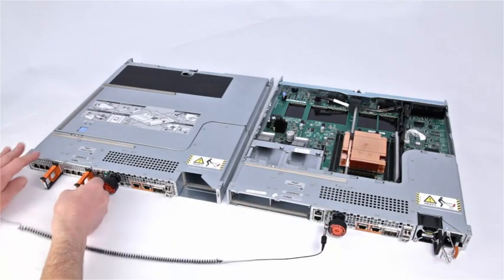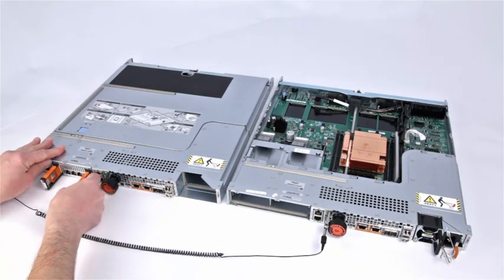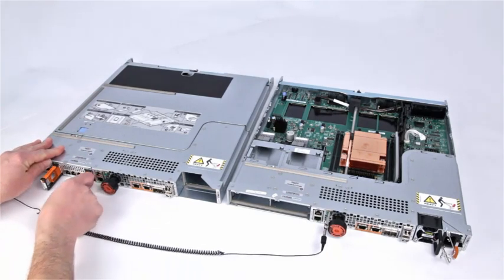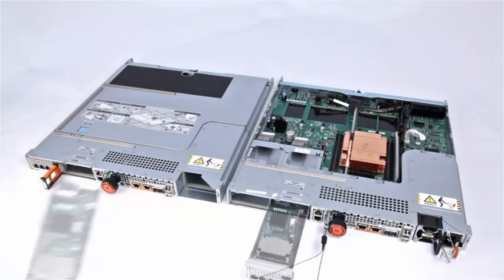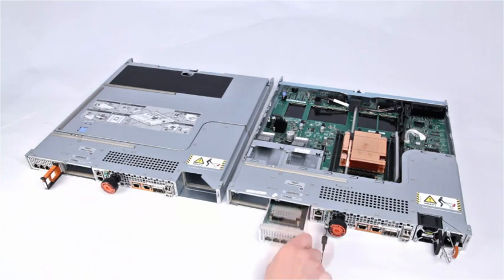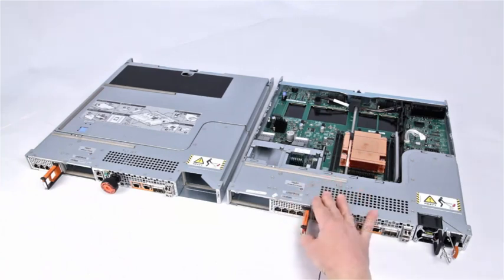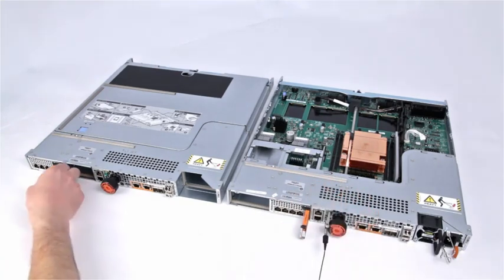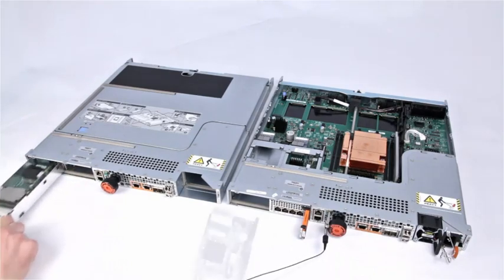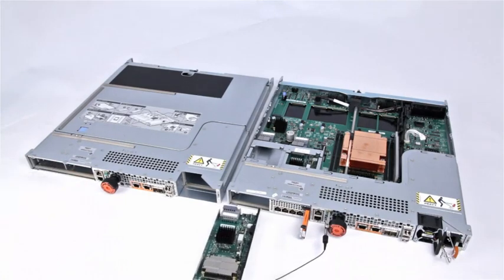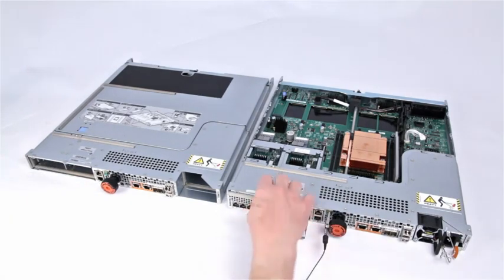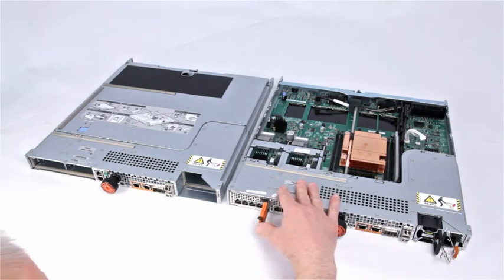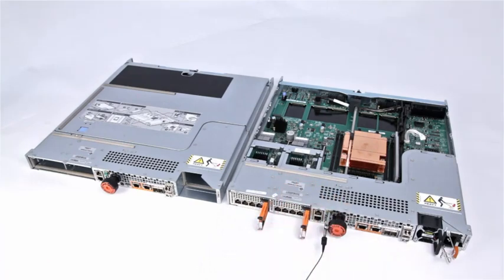Next, transfer each installed I.O. module to the exact same slot in the new SP assembly. Pull the trigger mechanism on the I.O. module handles to release them. Align the module with the empty slot of the replacement SP and carefully push the module into the slot. When the I.O. module appears seated, push and release the small button on the handle. If the button remains in, the module is fully seated.